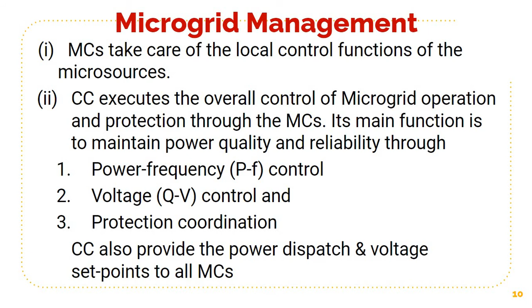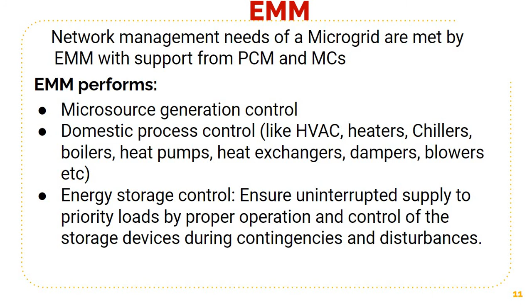The network management needs of a microgrid are met by the EMM with support from the PCM and microsource controllers. So the EMM, energy management module, performs microsource generation control, domestic process control like controlling the HVAC, heaters, chillers, boilers, pumps, heat exchangers, dampers, blowers, etc. Energy storage control is important to ensure uninterruptible power supply to priority loads by proper operation control of the storage devices during contingencies and disturbances, and maintaining the power quality.